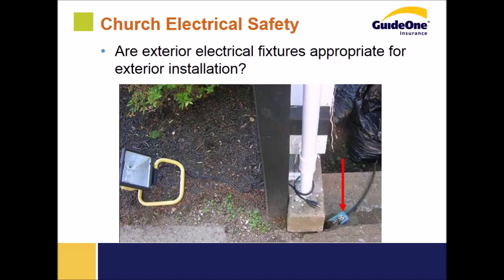Here's another example of temporary wiring being used as a permanent solution. They wanted to light their sign, so they used an indoor quartz work light plugged into a homemade extension cord. A couple of problems here: first, you've got an exterior condition. They're using inferior interior equipment, and it's not a permanent installation. Chances are it's not a ground fault circuit interrupter either—there's no ground fault protection on that cord.